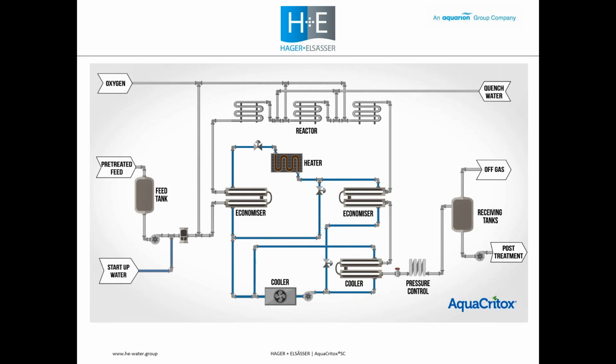So on startup, water's pumped to around 165 bar gauge, and the system begins to pass water. This is the start. At this point, we don't have process fluid running through the system, so we're getting the system ready for operation. The system will work with up to 50 grams per litre of COD and has a retention time of approximately 12 minutes.